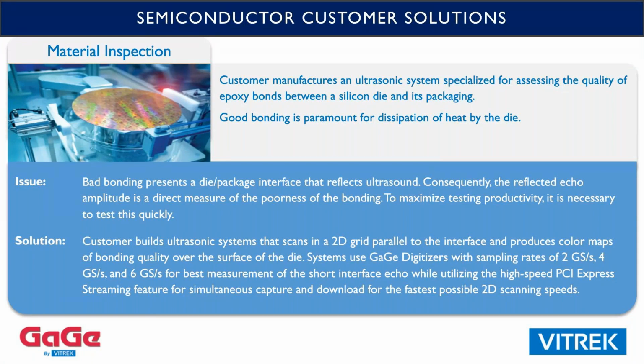In the scan, which might be several thousand points by several thousand points, the data are streamed off of the card very quickly. In the old days, you'd have to stop, download the data, whereas now with our streaming technology, we're able to offload the data from the card as it's being collected for the very fastest scan time. So that's another big advantage of the GaGe card, its fast data transfer speed for fast scanning. And of course, the high resolution to get the very smallest echoes from that bond to really judge that bond quality as best as we can. Next.